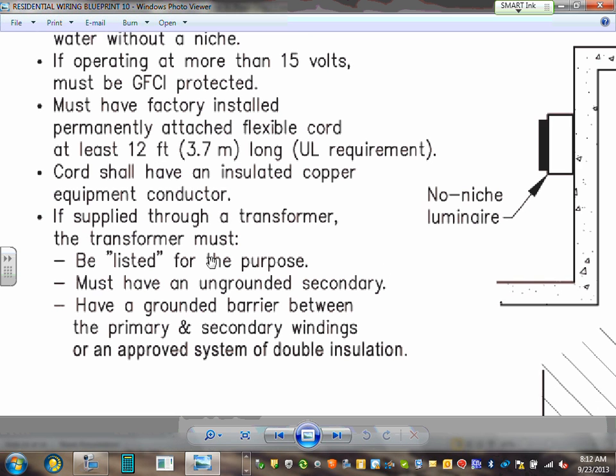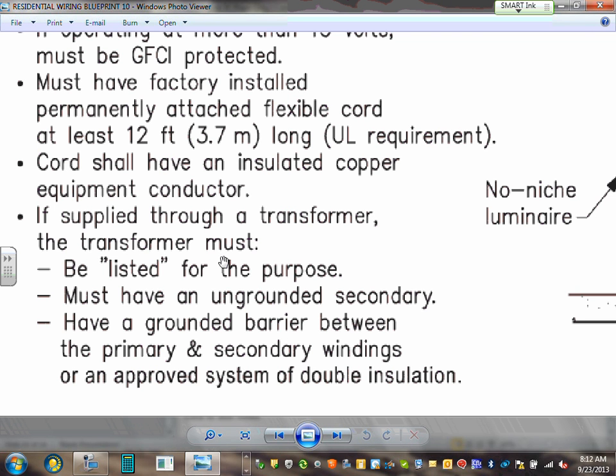So there's a whole lot of regulation, guys. Be listed for the purpose. Must have an ungrounded secondary. So it has to be fed from a transformer. Can you guys see that? And the transformer, an isolation transformer, has an ungrounded secondary and a grounded barrier between the primary and the secondary. So what they do, they have a transformer that takes the 120 or 277, 120 into a 24 volt, ungrounded, and they bring that to the light inside the swimming pool. By being 24 volt, it's safe for shock hazard, and by being ungrounded, guys, it doesn't shock you. It's not referenced to the ground. So they're very smart the way they do it.